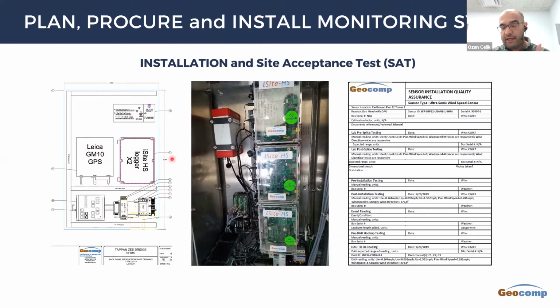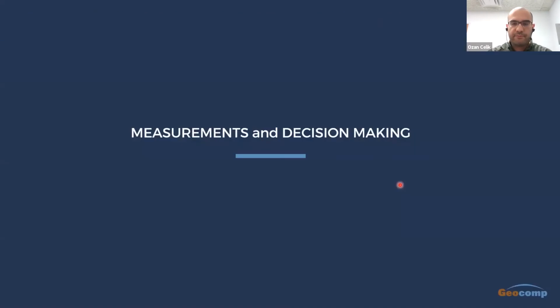And after this, having this factory acceptance tested, having the plan in your hand, you are going to go out there, install your system, and as we said, at every step of the way, you are going to record everything through a site acceptance test procedure. For each and every unit that you install out there, you are going to do your field tests and then record everything on your site acceptance test sheets so that they can be reviewed later on, which eventually is going to help you track what happened in the field, and if there's any problem, review those problems.